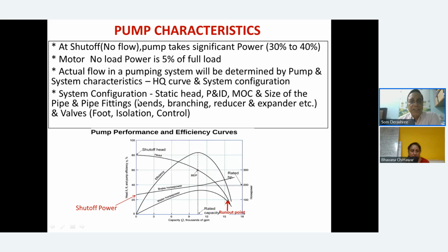Then system configuration. Actual flow in a pumping system will be determined by the pump characteristic of H-Q and the system configuration. System configuration is actually the static head needed, the P and ID, what the valves are, etc. Then what is the MOC, because the friction factor will depend on the MOC. What is the size of the pipe? What are the pipe fittings? What are the bends, branching, reducers, expanders, etc. that you put? What are the valves, that is foot valve, isolation valve, control valve that you...